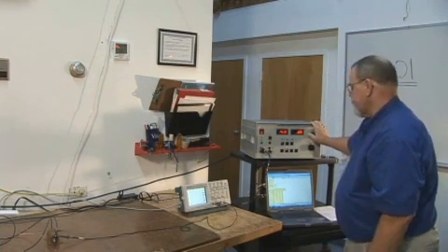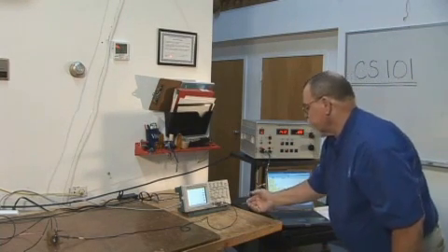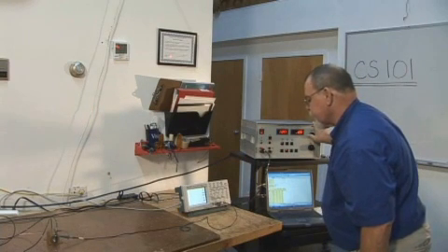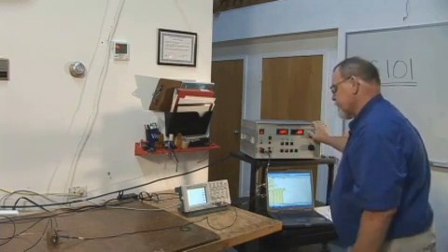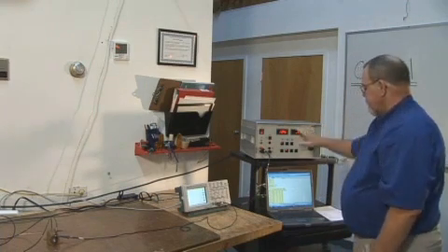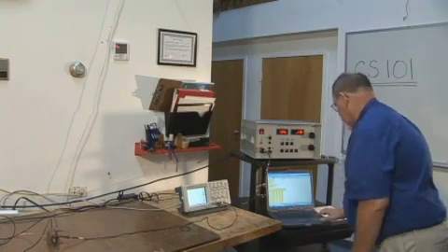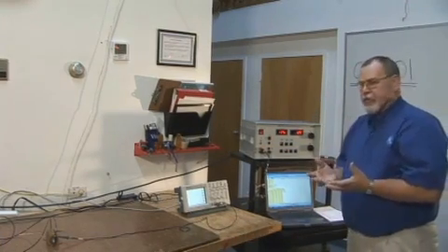So there's 6.32 volts, actually slightly above, and I want to be slightly above. Remember, I'm doing susceptibility. So there's 6.37 volts. My voltmeter says 13.95. I record that number. I go on to the next frequencies.